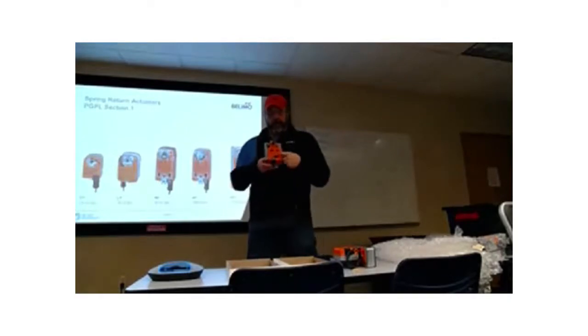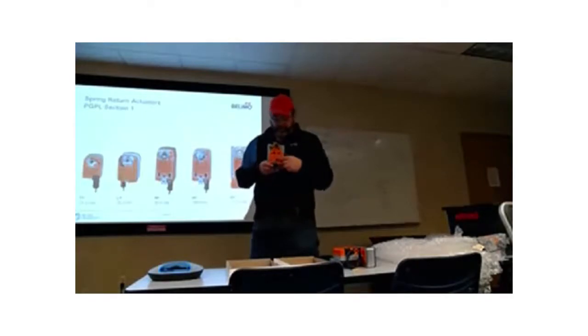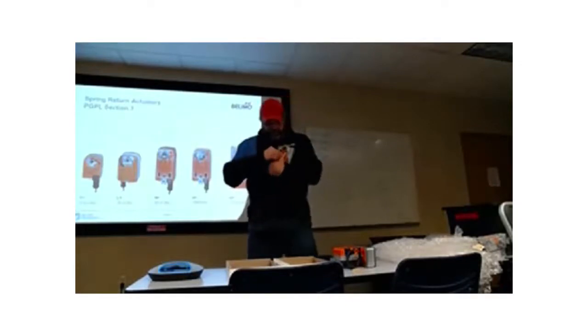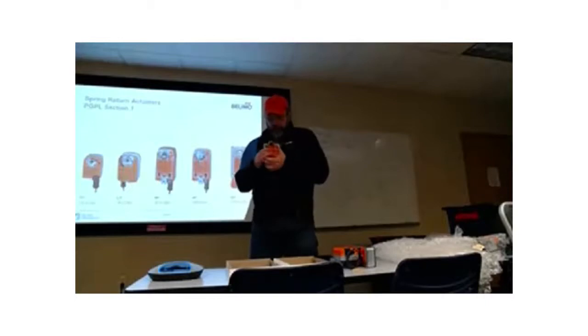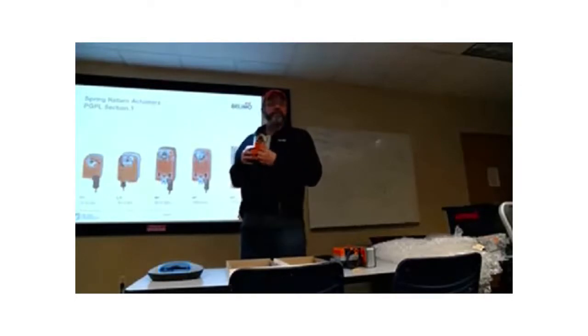Sort of looks like a dually here, the wide body actuator. The capacitors sit right here, inside. If you look at the switch on the front, there's a little plastic window. This is where you adjust the actual fail position of the actuator. You can set it in 10-degree increments all the way from 0 to 90.